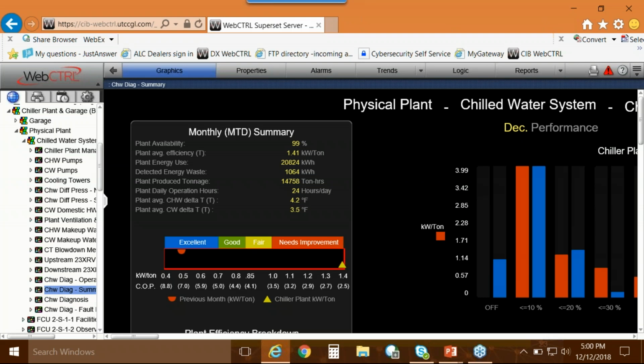We're running this right now in the WebCTRL platform, but we're also uploading it onto a cloud server. We're also embedding some of it into the Carrier service organization that wants to know lots of stuff about the chiller, which they do, but they don't have fault detection and diagnostics. They're using it to proactively show up to repair something or avoid a failure, to only show up when service is needed. We're trying to have them use the fault detection and diagnostic component to increase their value to the customer and not send out service contractors when they're not needed.